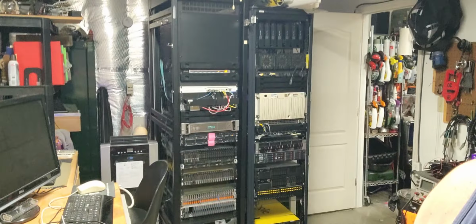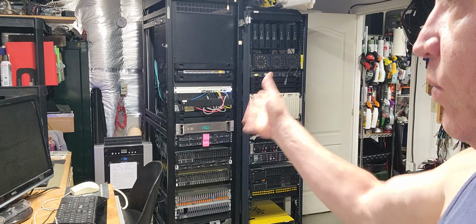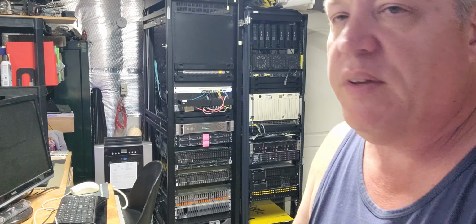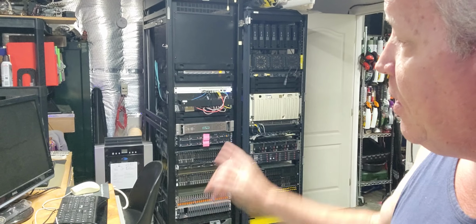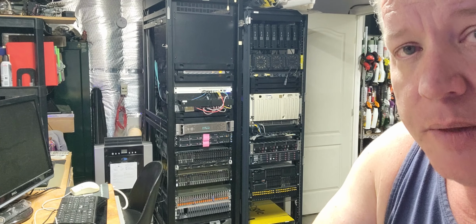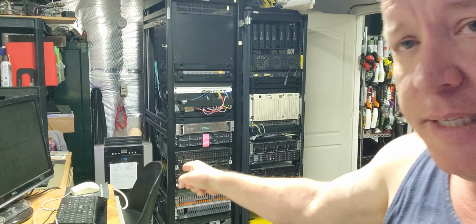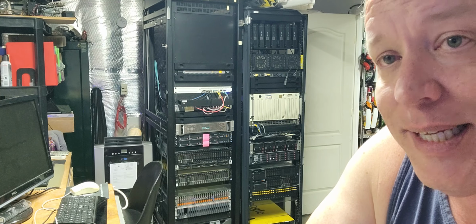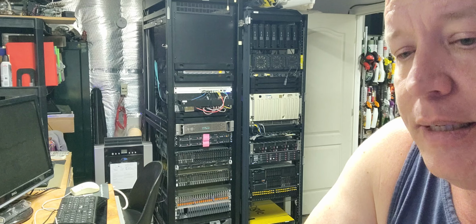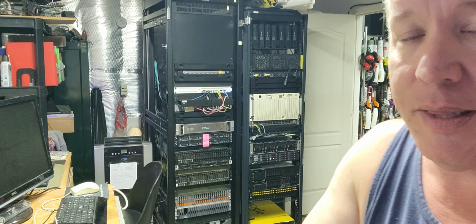In my data center here, that little guy down there will cover this entire room plus 20% more, which means I want to run it at about 50% capacity. By running at 50% capacity, that unit will run me for 10 years. If I got my square footage too close to how many BTUs this guy can handle, I would have the lifespan of a 2 to 3 year window because I'd be running it harder and wearing it out faster. It's the same principle as we do with hard drives and everything else.